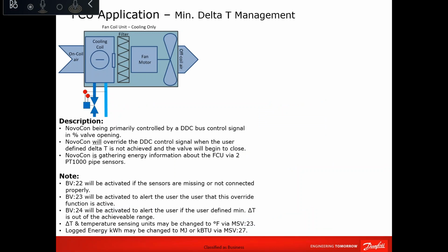So it will look like this: Novocon is primarily controlled by the DDC or a control signal via percentage of opening. Novocon will override the DDC control signal when the user-defined delta T is not achieved, and the valve will begin to close. Novocon is gathering energy information about the FCUs via 2 temperature sensors, or about the area where it is installed. It's not necessarily an FCU. When this is happening, you will have an alarm on whether the sensors are connected or not, and an alarm that delta T management is active, it is working, and so on.